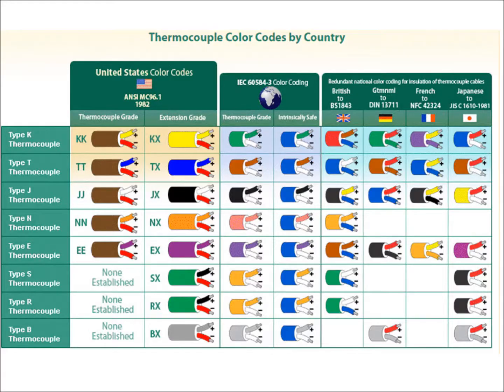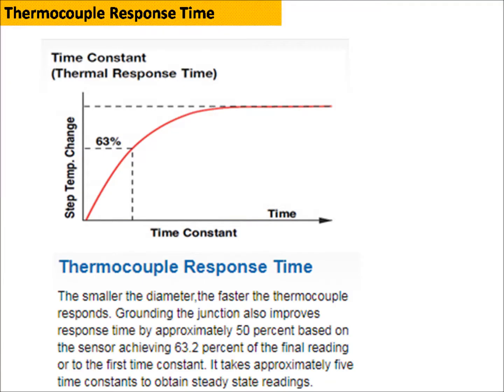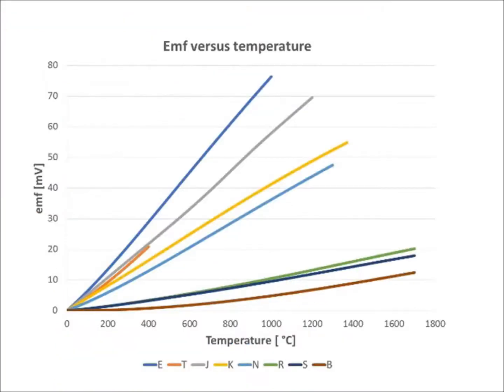Thermocouple color codes differ from country to country. The time constant is defined as when the sensor achieves 63.2% of the final reading. A smaller time constant means a better response from the thermocouple. An EMF versus temperature curve is available for different types of thermocouple.